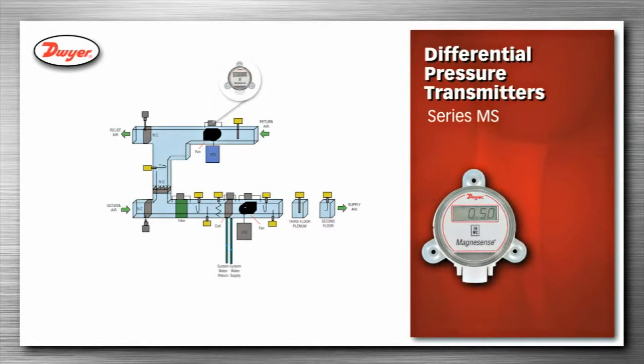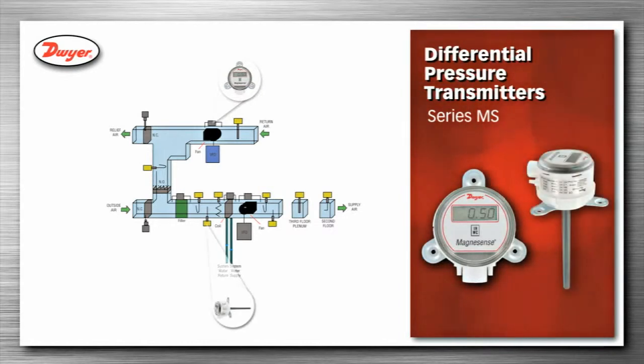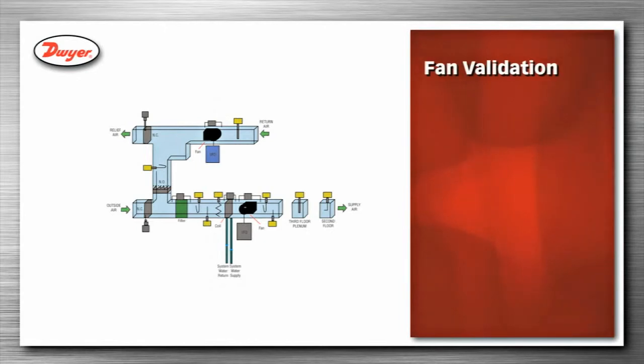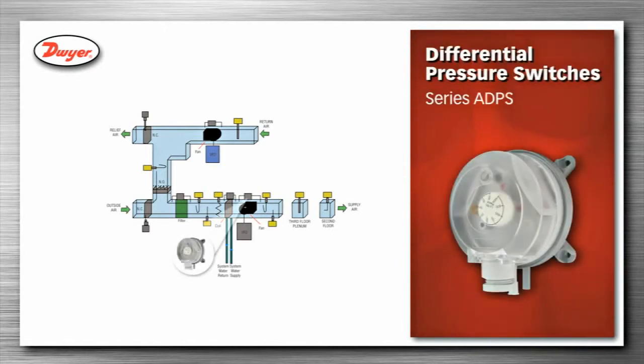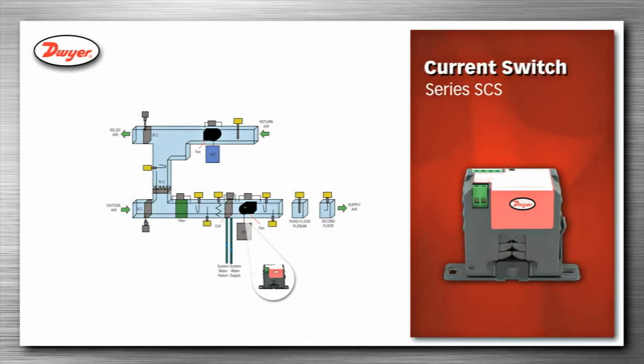Differential pressure transmitters, Series MS, are used with a static pressure sensor or with inherent static probe to monitor discharge air and mixing air duct static pressures. Dwyer offers several products that can be used for fan validation, proving that the fan is operating. The differential pressure switch Series ADPS can be used by monitoring the differential pressure between upstream and downstream of the fan. Series SCS current switch can be used by monitoring the current usage of the fan.